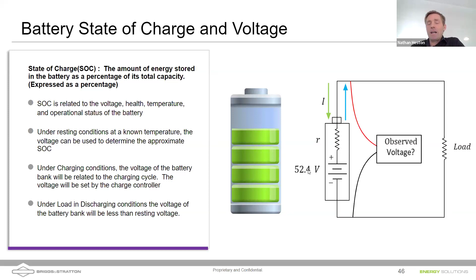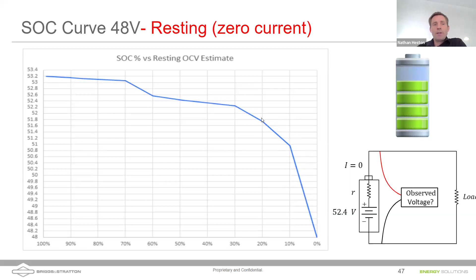And so what happens when current is flowing out of a battery, as in the case of the blue arrow, there's a loss of voltage across the internal resistive parts of the battery. And when current is flowing into the battery, there's a gain in voltage across the internal resistance. So I might see the voltage of the cells plus something when I'm in a charge cycle. And if I'm in a discharge cycle, I'd see the voltage of the cells minus something. So let me illustrate that. This is resting voltage. You should see voltages at around 100% state of charge, starting at a little above 53 volts. And then it drops off fairly slowly until you get to around 80 or 90% discharge, right? And then we hit what we call the knee here. It drops off really quickly after that. We do recommend, if you're charging and discharging your batteries daily, to not drop below this part of the knee. So this is a resting battery curve.